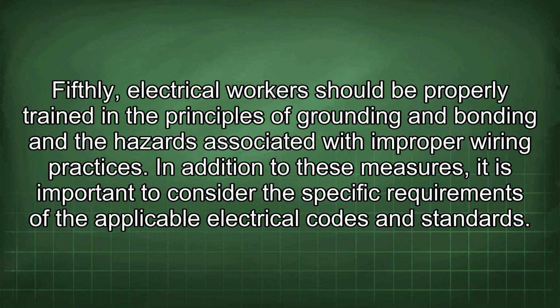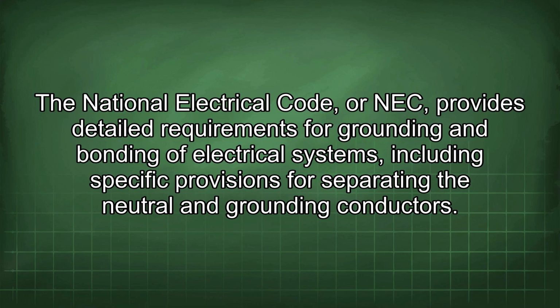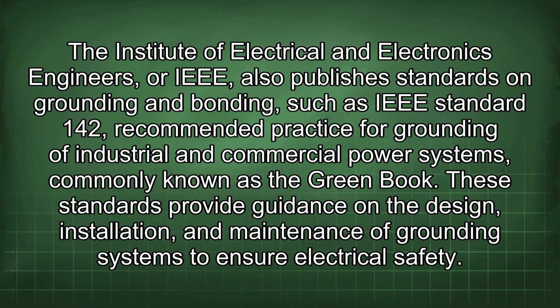and standards. The National Electrical Code, or NEC, provides detailed requirements for grounding and bonding of electrical systems, including specific provisions for separating the neutral and grounding conductors. The Institute of Electrical and Electronics Engineers, or IEEE, also publishes standards on grounding and bonding, such as IEEE Standard 142, Recommended Practice for Grounding of Industrial and Commercial Power Systems, commonly known as the Green Book. These standards provide guidance on the design, installation, and maintenance of grounding systems to ensure electrical safety.